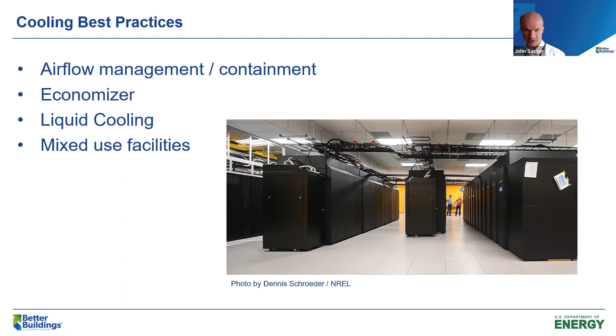Next slide, please. This is a non-contained environment, really common around 2000 to call it 2010. At least in this case, you've got the hot air facing each other. But where that guy is standing, you're doing a lot of mixing of air. What that means is you have to provide cooler air through that floor tile, very common to have it less than 60 degrees, and you're going to run more fan energy.